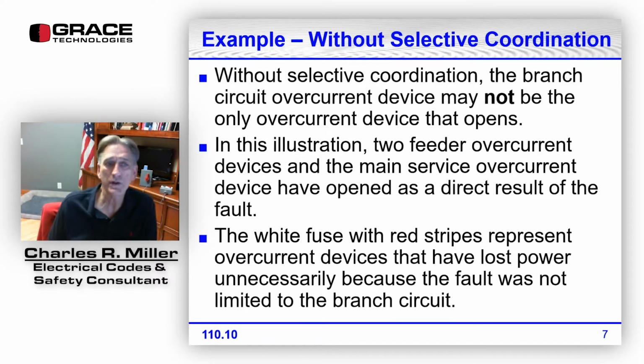All right, so here's an example. Without selective coordination, the branch circuit overcurrent device may not be the only overcurrent device that opens. In the illustration on the next slide, two feeder overcurrent devices and the main service overcurrent device have opened as a direct result of the fault, because selective coordination was not implemented into the electrical system. In the next slide, the white fuse with red stripes represents overcurrent devices that have lost power unnecessarily because the fault was not limited to the branch circuit.